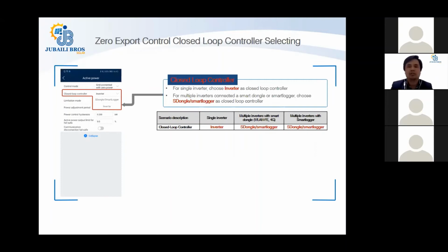Zero export control, closed loop controller. You must select the type of closed loop control that you will have in your PV system, because the system is not as intelligent as you are. You have to tell the system exactly whether the control will happen with the inverter or from the smart logger or dongle. If you have more than one inverter, you will choose the smart dongle or smart logger option under the closed loop control. Otherwise, if you have a single inverter in your PV system, then for the closed loop control, you will select the device, the inverter.